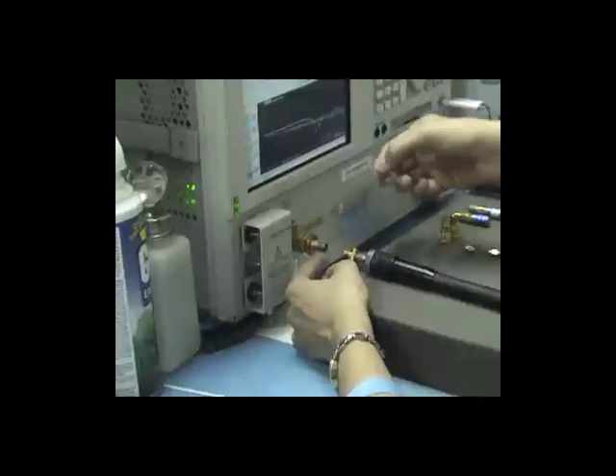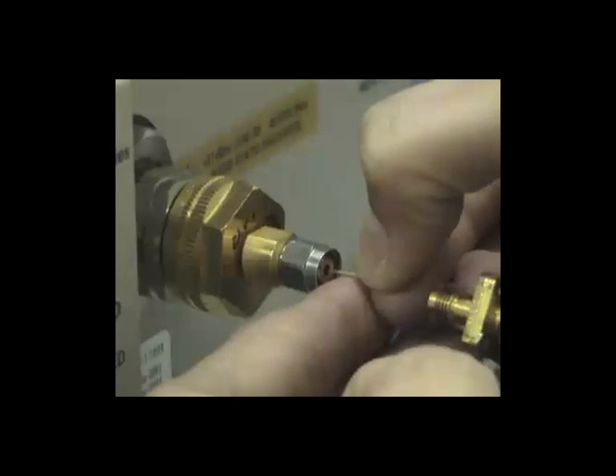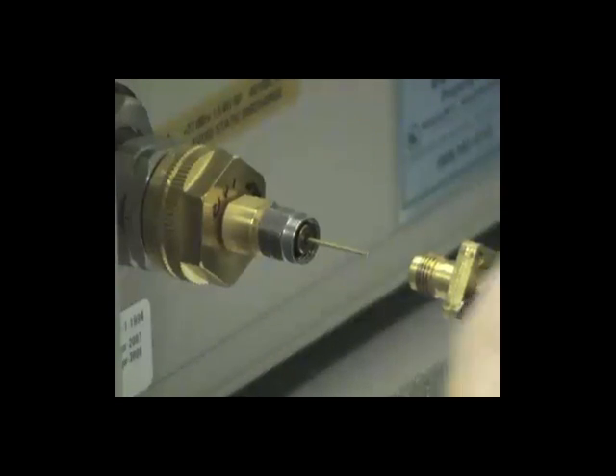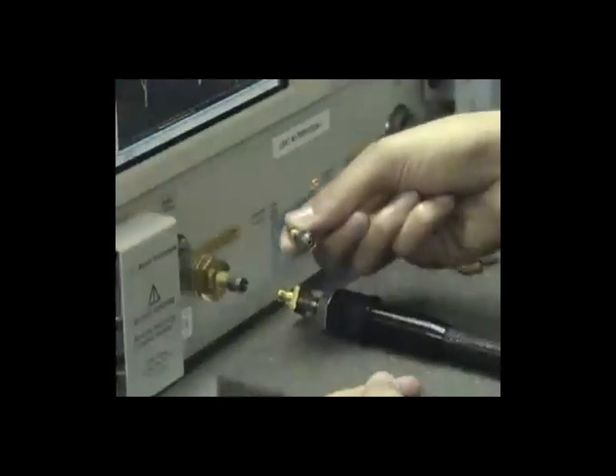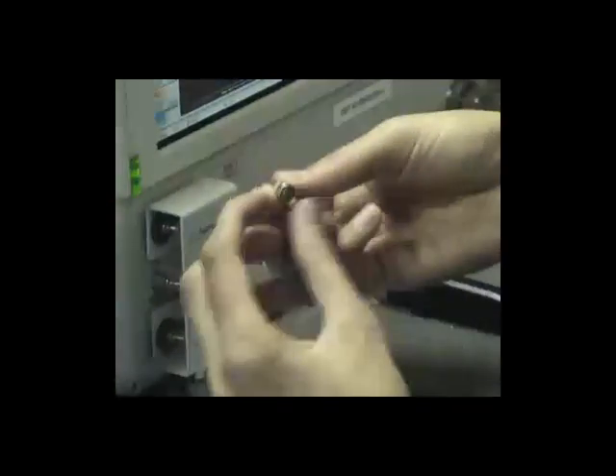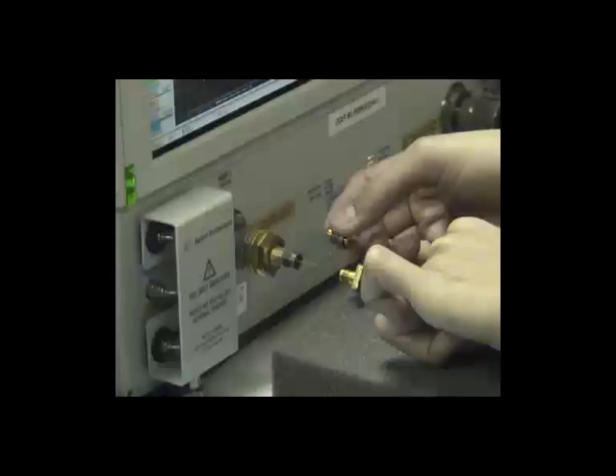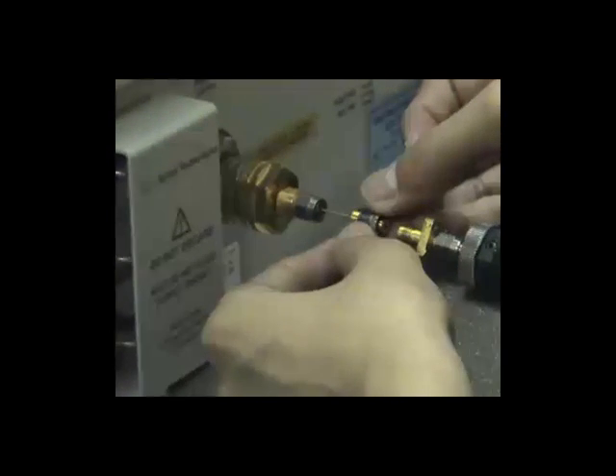Moving on to the second airline, 1.15. Make sure you just touch any ground surface and then connect it, go as straight as possible. These bodies have a retractable coupling nut that moves forward and backward. It's basically designed this way to make it easier for the connection, because if the coupling nut is in its forward position it would be harder for you to align it with the port. Again, slide the cable backwards so you'd have enough room to work and try to get it as centered as possible.